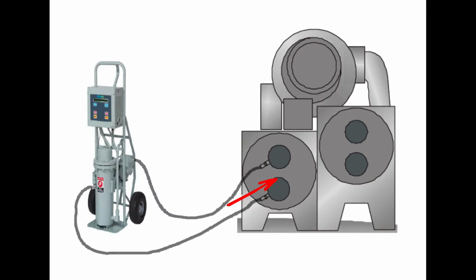Now you're isolating both of your barrels, and when you're doing this, at least I personally, I want to have both barrels completely isolated. I don't want the heat I'm putting into the machine to be able to trickle out into the rest of the water loop. And if your ISO valves on the barrels are not holding very well, especially the chilled water barrel, this whole process is just not going to work. You're not going to be able to get enough heat flowing through there to get the machine's pressure up, because even if it's just a bleed by on the valve, it's going to keep enough cooling going through there.